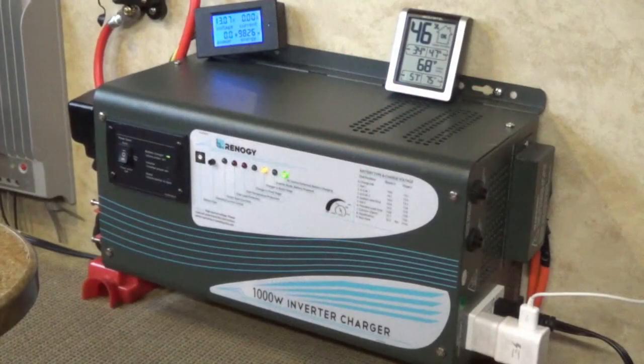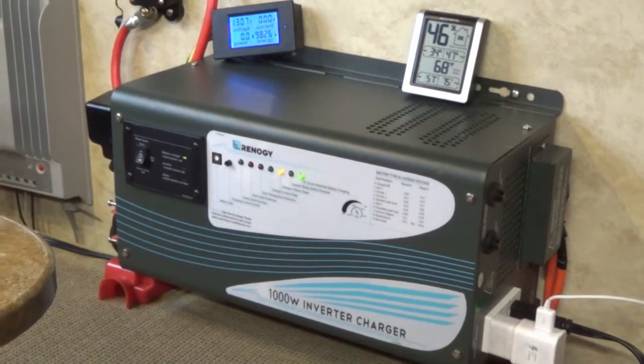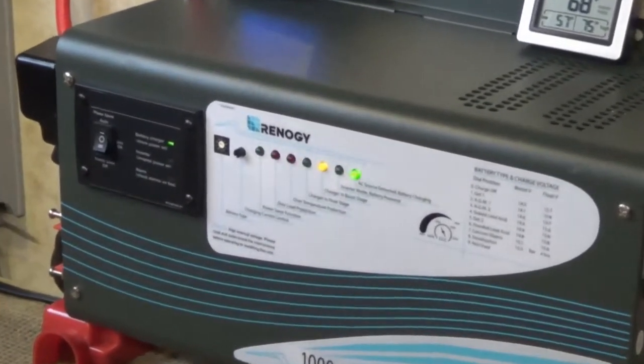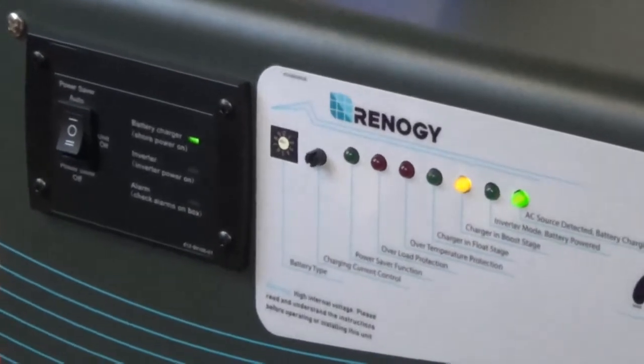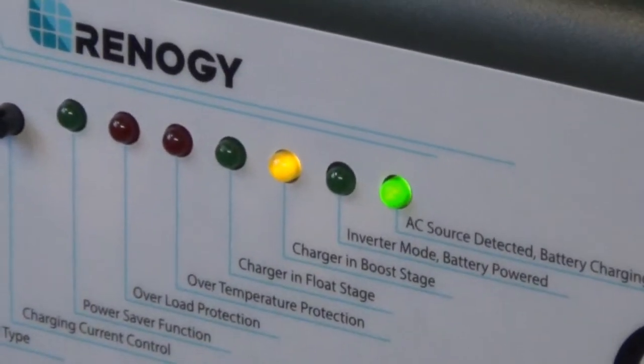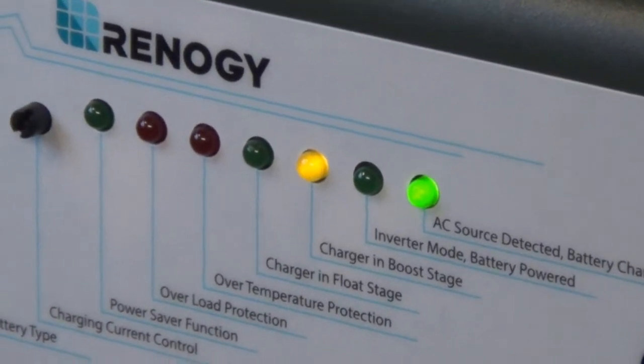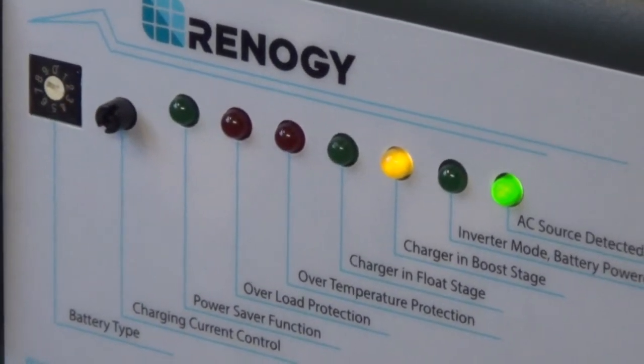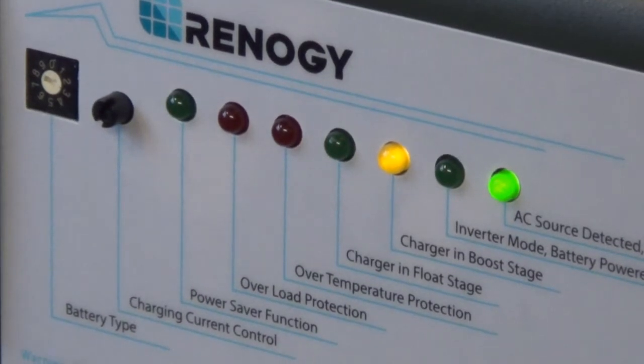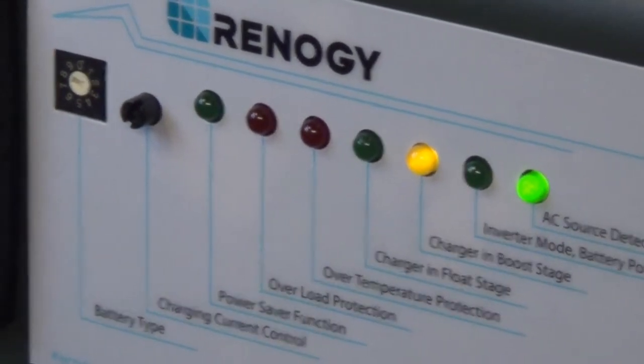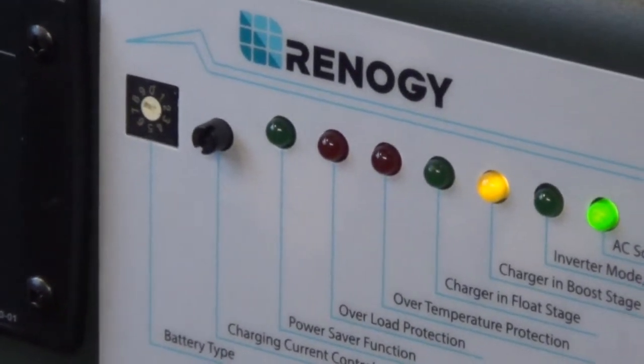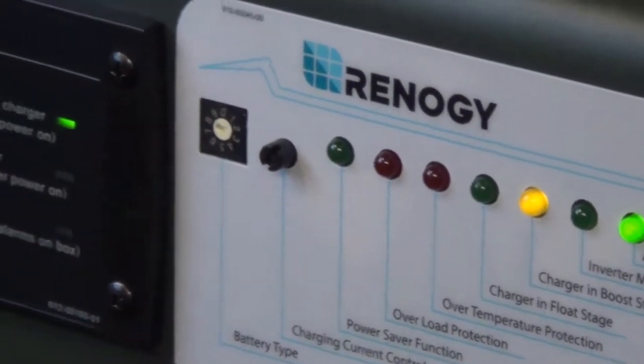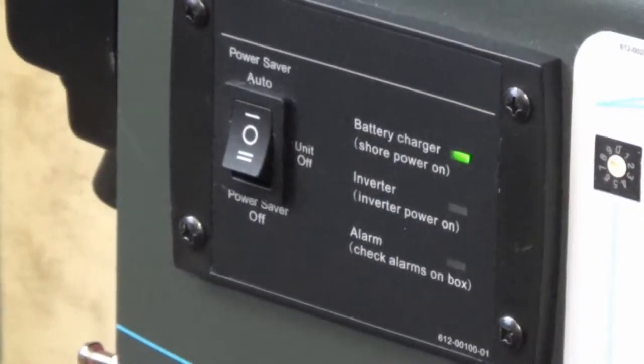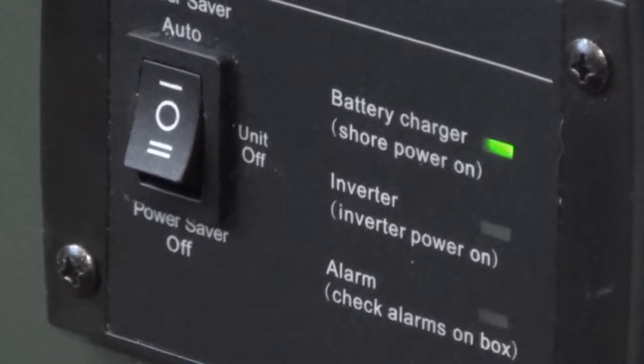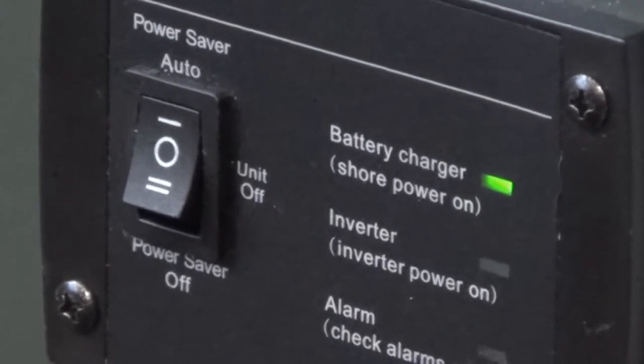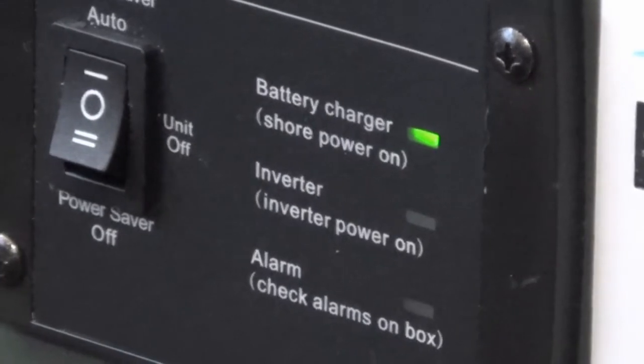One of the interesting dip switch settings is that you can tell it to select between AC priority and battery priority. Right now you can see it's showing an AC source detected charging, and what I did is I switched it from battery priority, which tells the unit to take current from batteries first, and then when the batteries get down too low, it'll switch to AC if one is detected. The other choice is AC mode, where it will run strictly off of AC, and then if you lose AC power, it'll switch to battery mode.